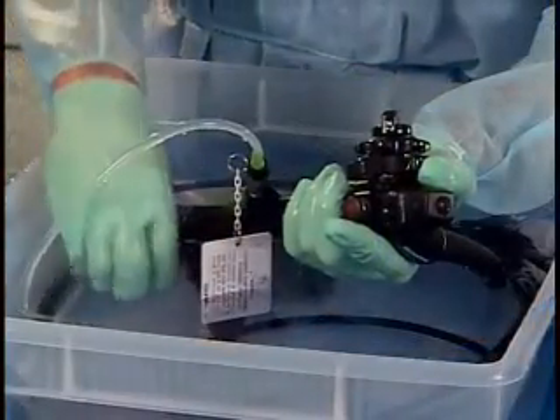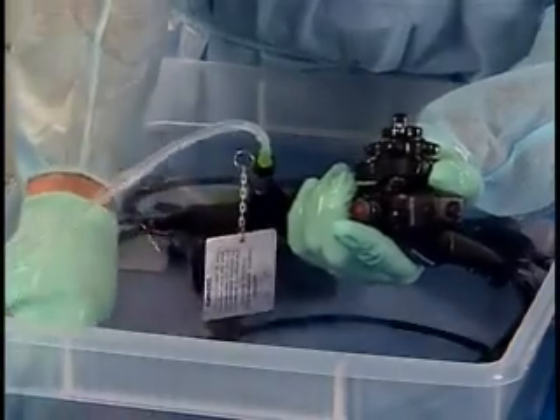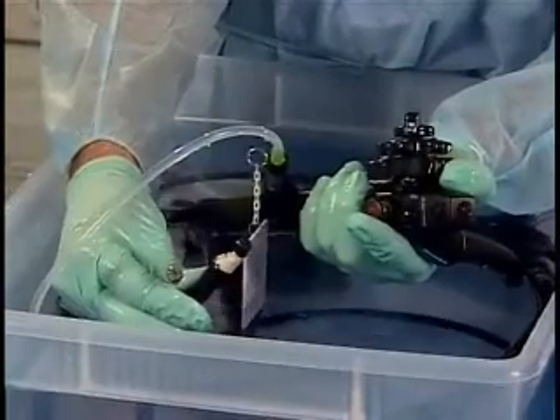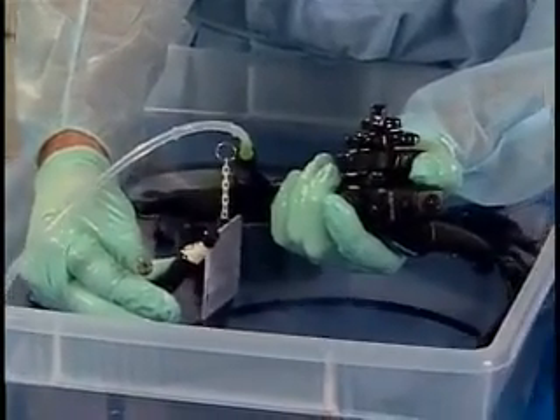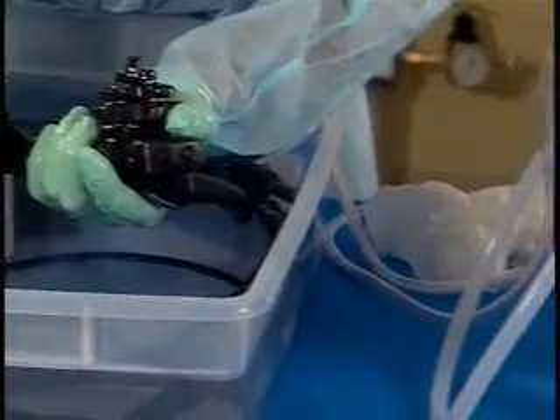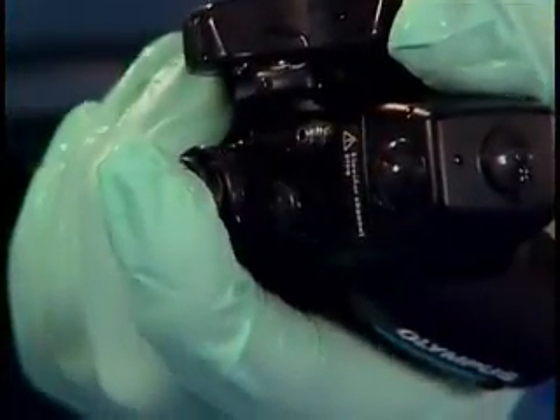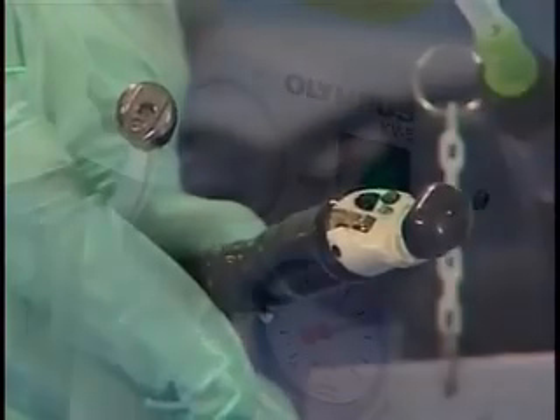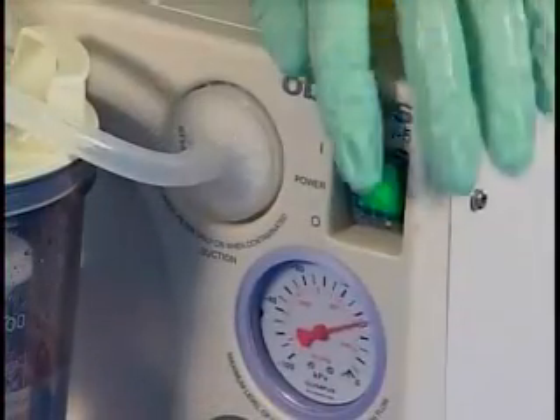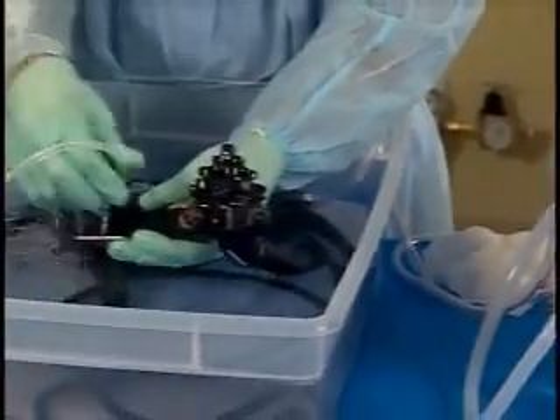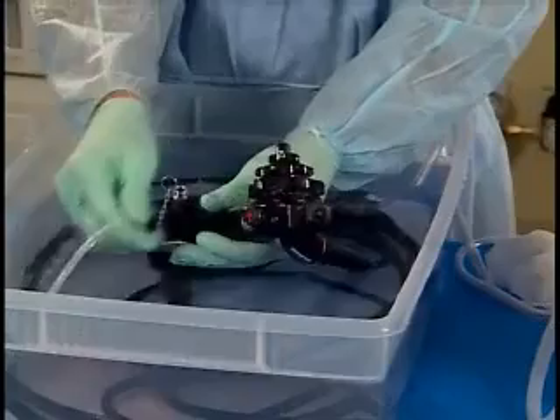Remove the endoscope's distal end and the end of the suction cleaning adapter from the detergent solution. Aspirate air into the instrument channel for 30 seconds. Depress the suction valve completely and aspirate air through the balloon suction channel for 30 seconds. Turn the suction pump off and disconnect the suction valve and tube.